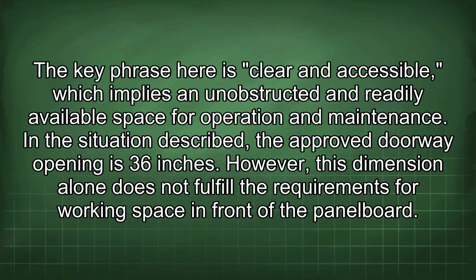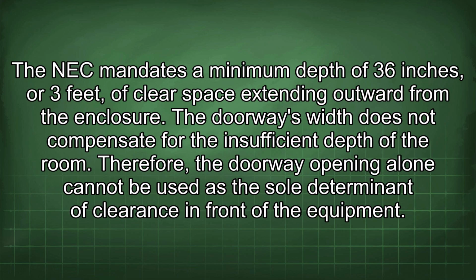In the situation described, the approved doorway opening is 36 inches. However, this dimension alone does not fulfill the requirements for working space in front of the panelboard. The NEC mandates a minimum depth of 36 inches, or 3 feet, of clear space extending outward from the enclosure. The doorway's width does not compensate for the insufficient depth of the room. Therefore, the doorway opening alone cannot be used as the sole determinant of clearance in front of the equipment.